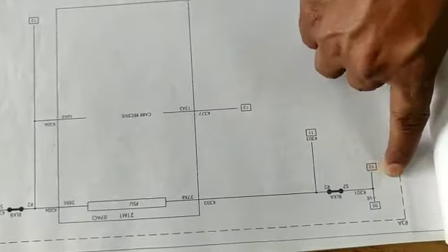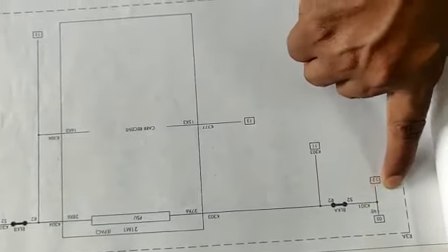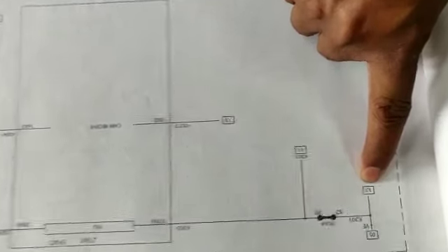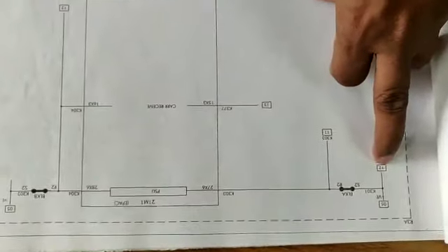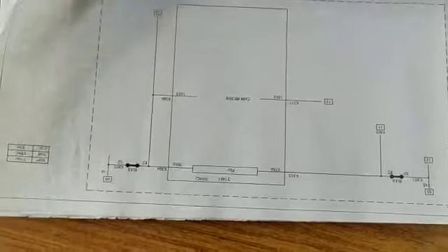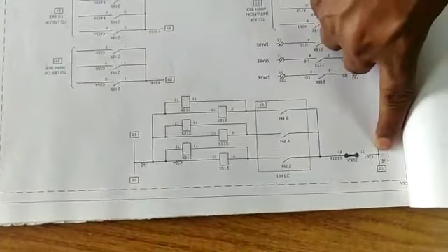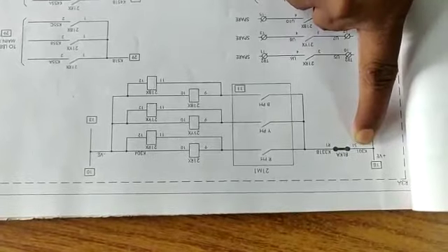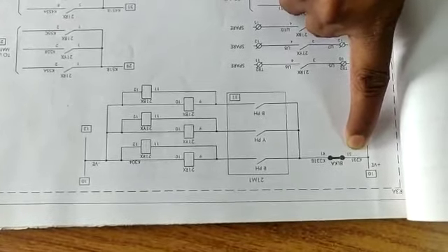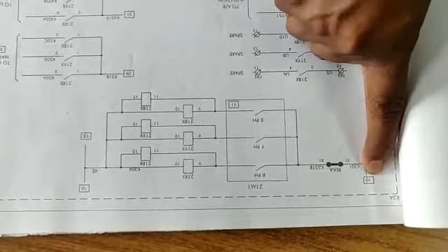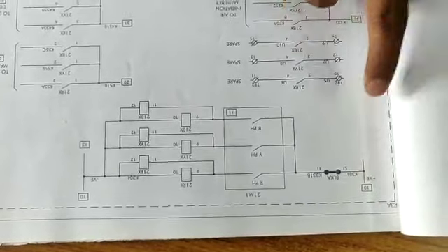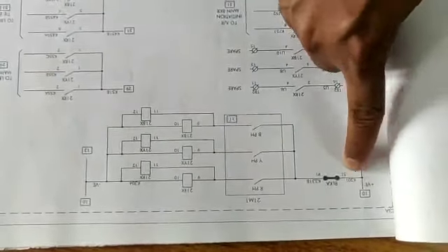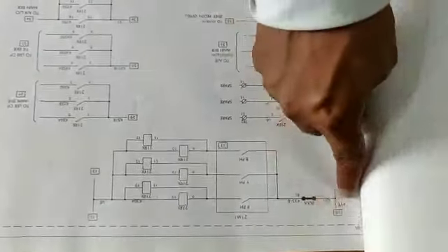Now there is another number written just below this line, again a rectangle marked as 12. If you see this number marked as 12, that means if you refer to page number 12, you can see that this DC supply is extended from this page to the next page. Now if you look here, this is positive voltage K301, that means the positive DC supply, and it is coming from page number 10. K is again for control, or for binary input, binary output, anything. This is for control.